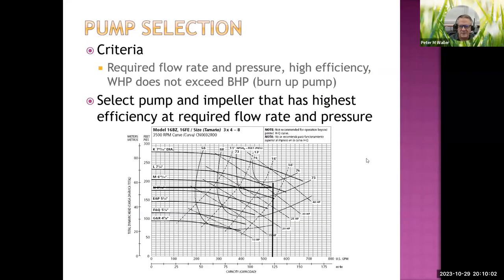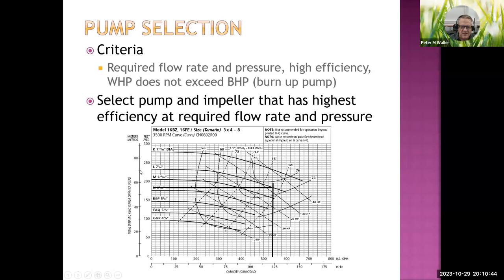The criteria for pumps are established by the irrigation system — there's a required flow rate and pressure for each zone. You also want to shoot for the highest efficiency. Looking at pump curve charts, you scan through pump catalogs and pick the best pump that matches your system requirements. For example, this pump has 76% efficiency at about 500 gallons per minute and 70 meters of head. You find the pump that has its sweet spot near your desired operating point.